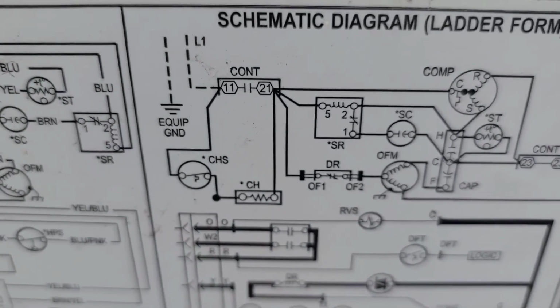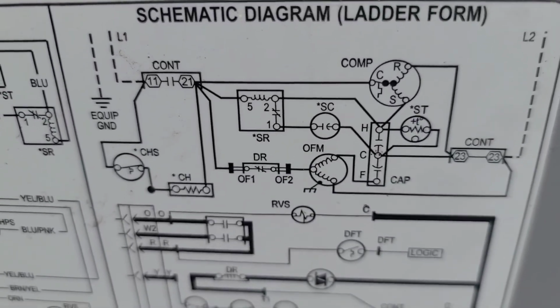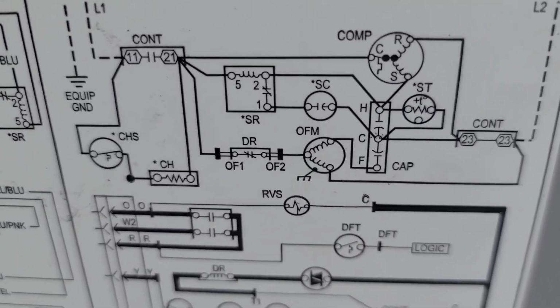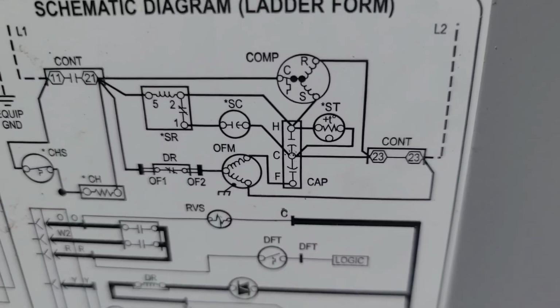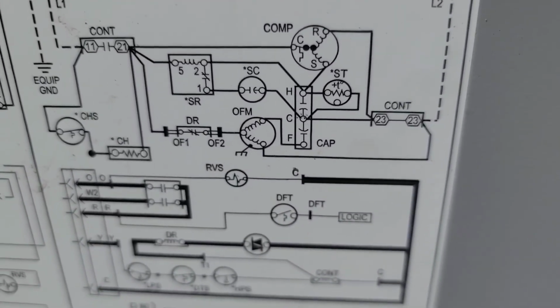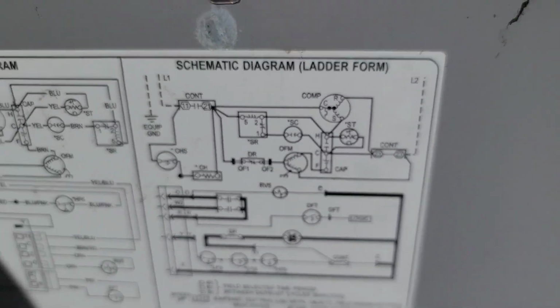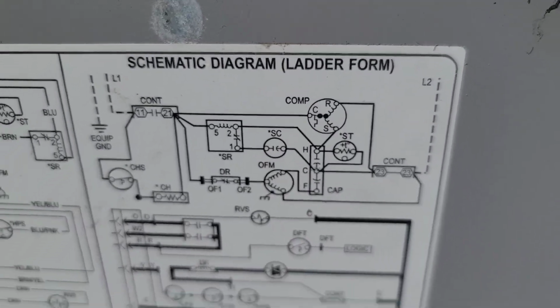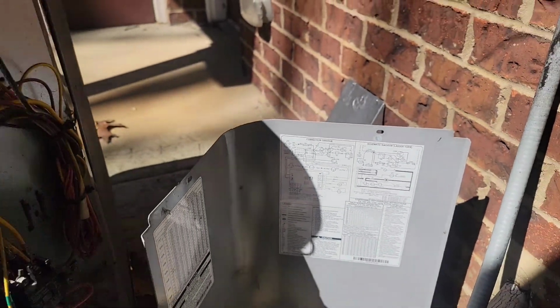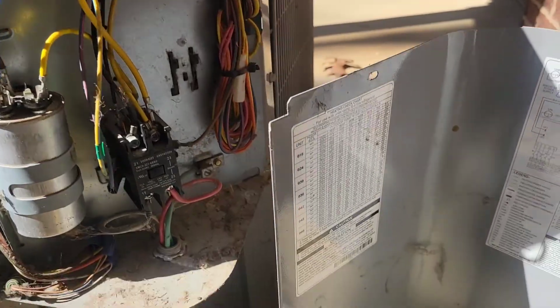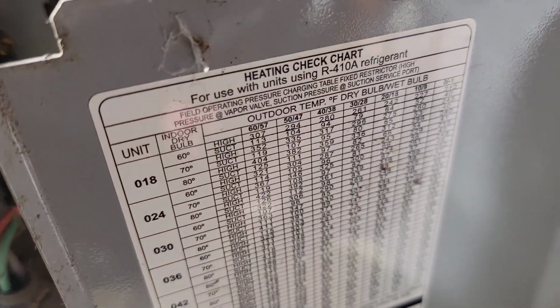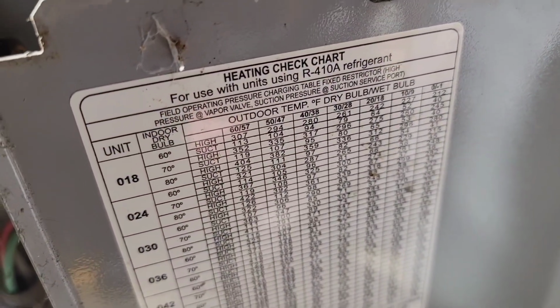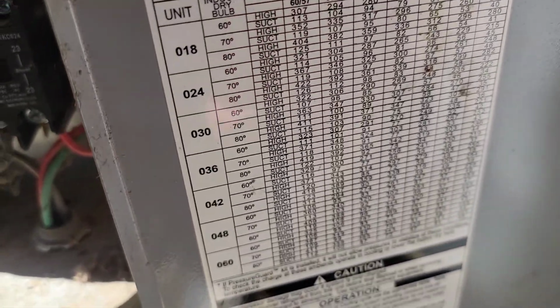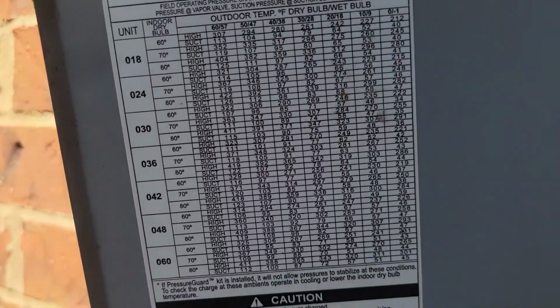Crankcase heater, contactor, compressor. We don't have a potential relay or a start capacitor. We've only got a dual capacitor. So you see where it says HCF cap? That's what we've got. There's our compressor, COMP. A little bit of reading on that schematic for you. And we've also got heating check chart for use with units using R410A. So this chart is very useful for charging.